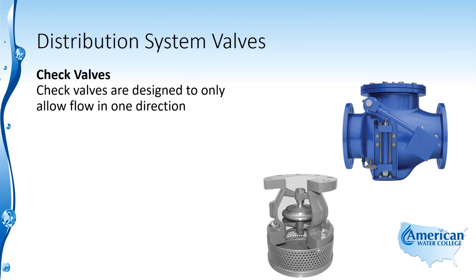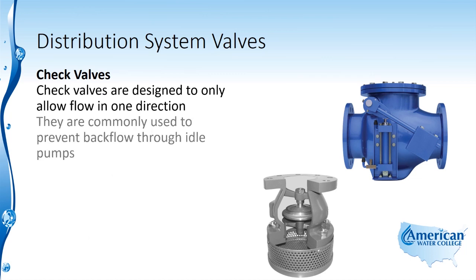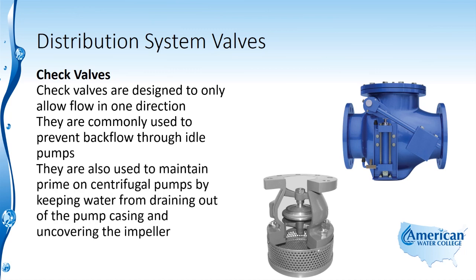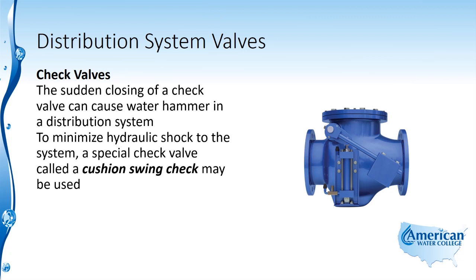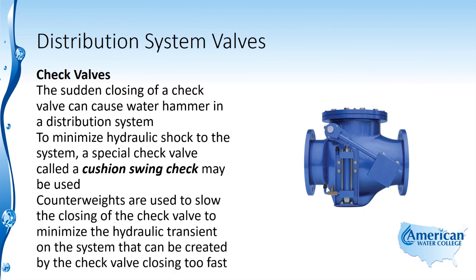Check valves are designed to only allow flow in one direction. They are commonly used to prevent backflow through idle pumps and to maintain prime on centrifugal pumps by keeping water from draining out of the pump casing and uncovering the impeller — this type is called a foot valve. The sudden closing of a check valve can cause water hammer in a distribution system. To minimize hydraulic shock, a special check valve called a cushion swing check may be used. Counterweights are used to slow the closing of the check valve to minimize the hydraulic transient created by the valve closing too fast.